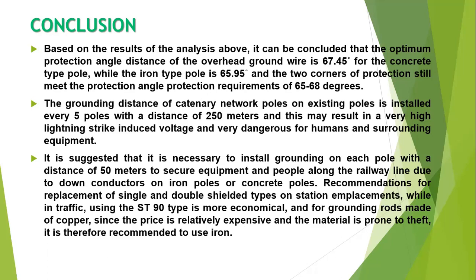The grounding distance of catenary network poles on existing poles is installed every 5 poles with a distance of 250 meters, and this may result in a very high lightning strike induced voltage and be very dangerous for humans and surrounding equipment. It is suggested that it is necessary to install grounding on each pole with a distance of 50 meters to secure equipment and people along the railway line, using down conductors on iron poles or concrete poles.